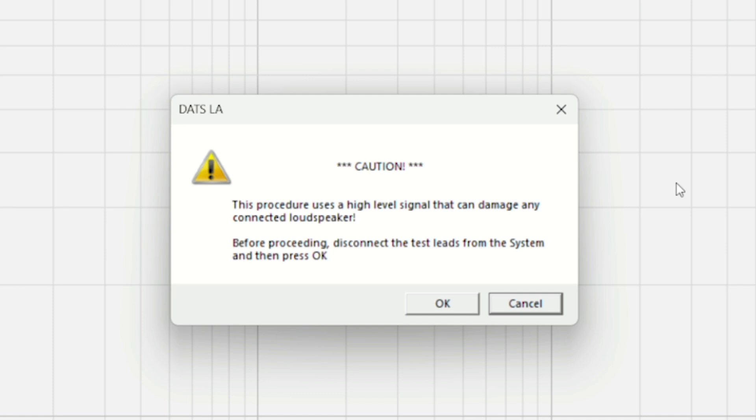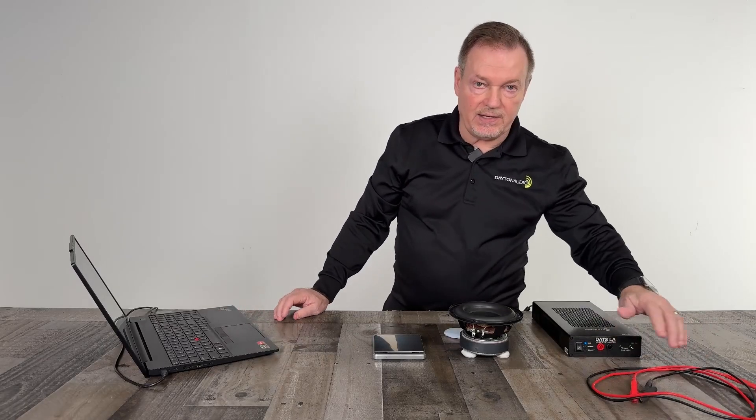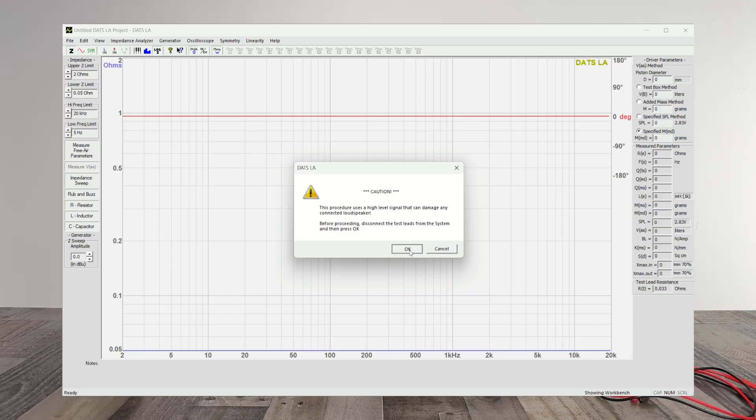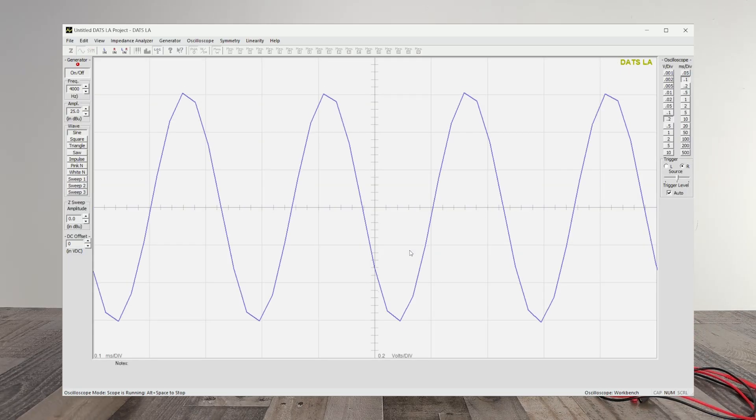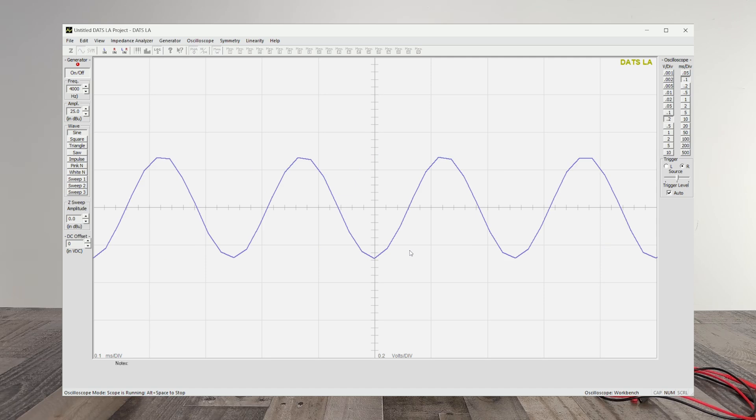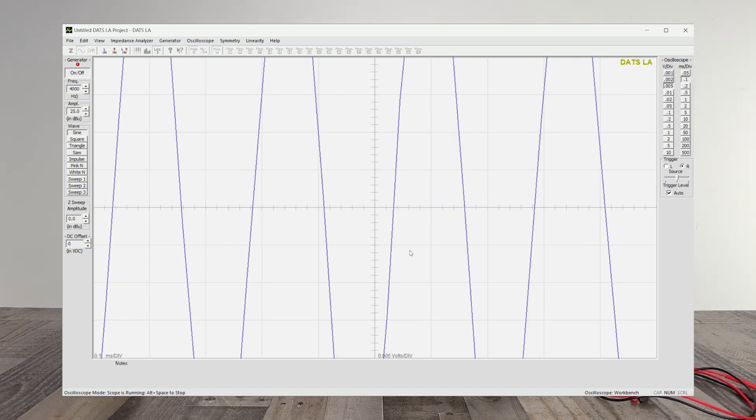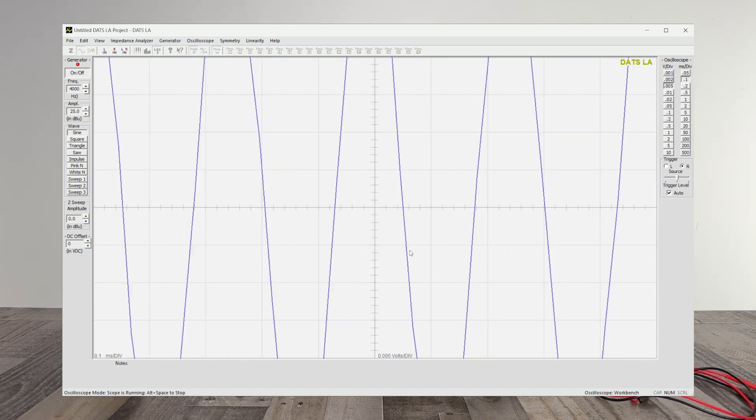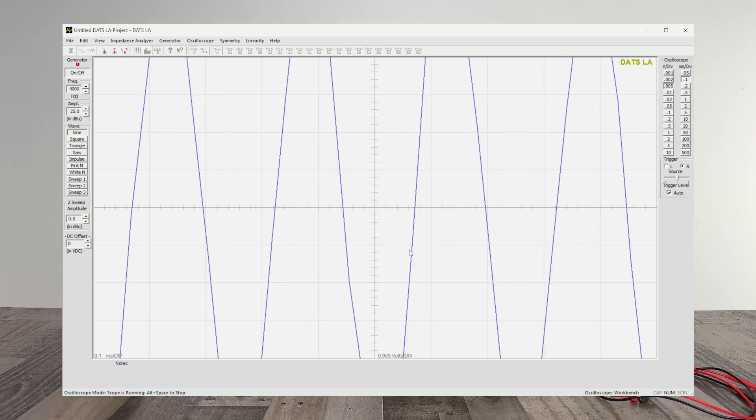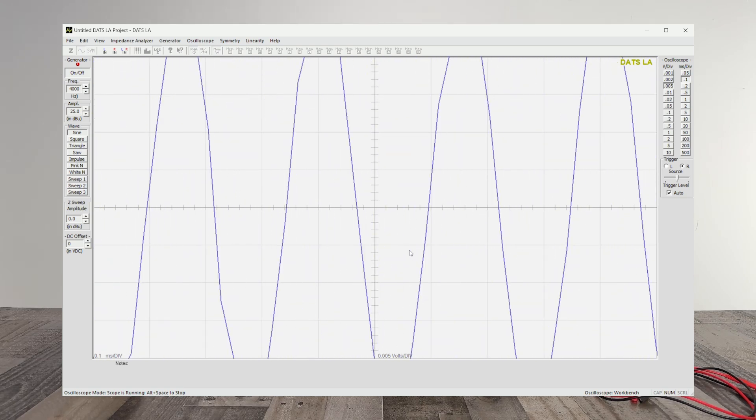Now it's going to ask you, make sure it's not connected to anything, which you can see the test leads are not connected. Nothing's connected. You click OK, and it's going to do a large signal at 4,000 Hertz. It moved over to the generator screen to do this. So you can see it reacting. You can maybe hear the 4,000 Hertz at high level.